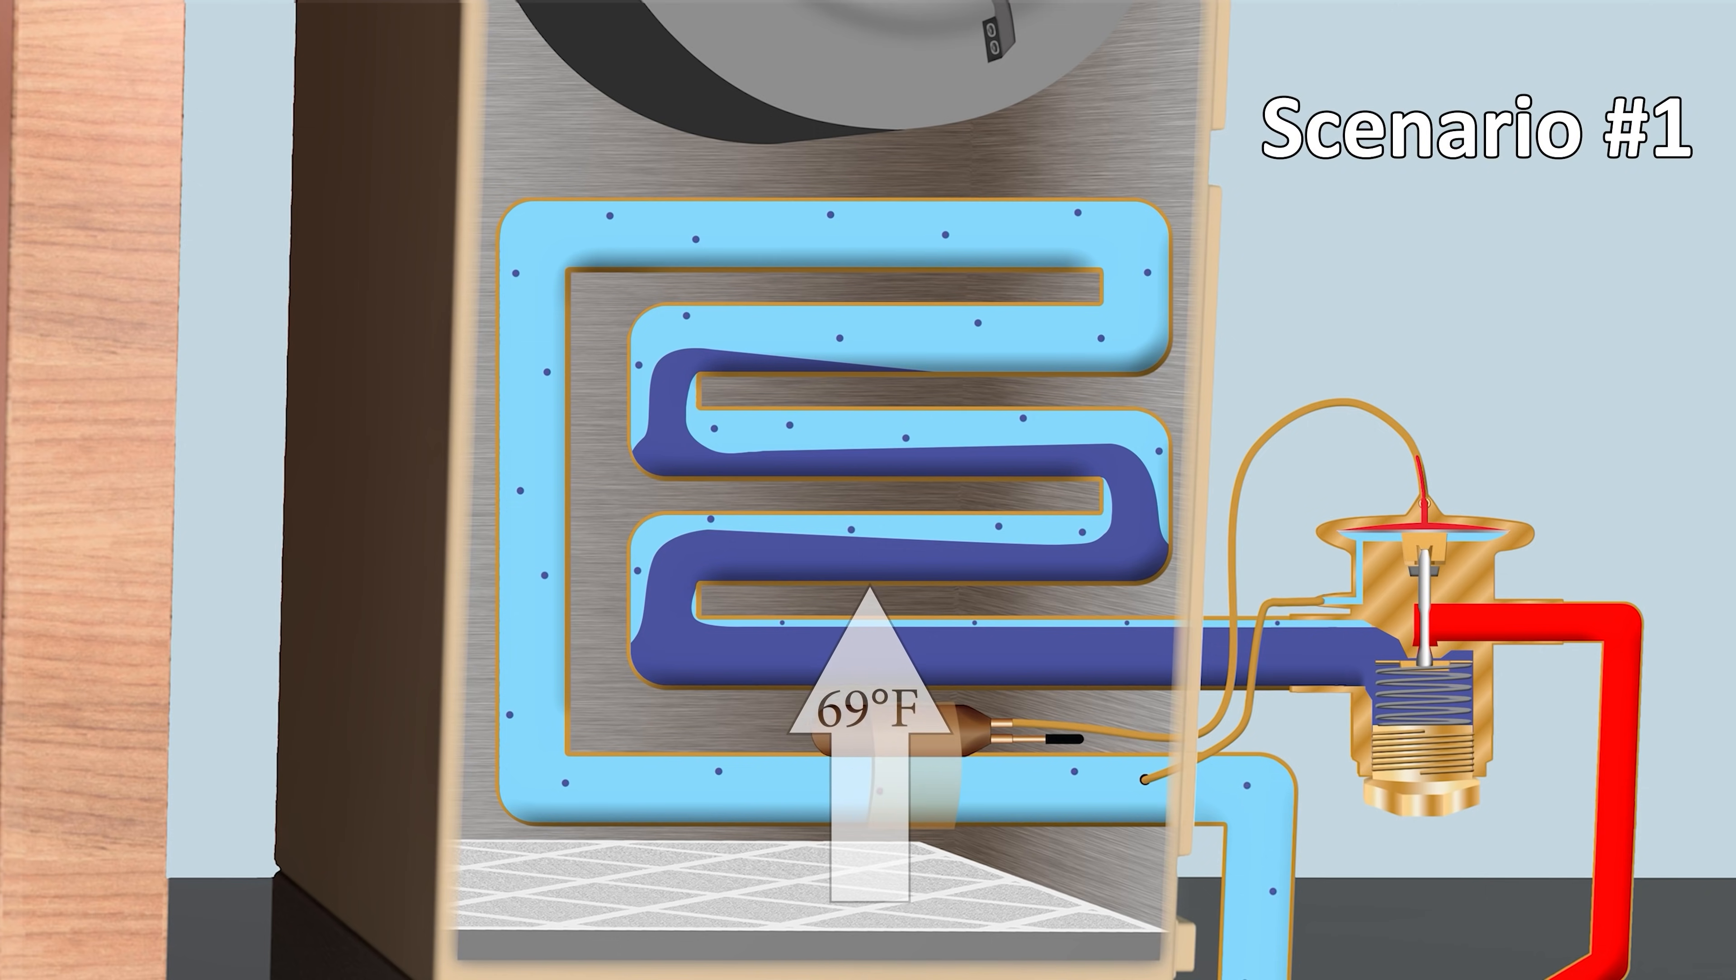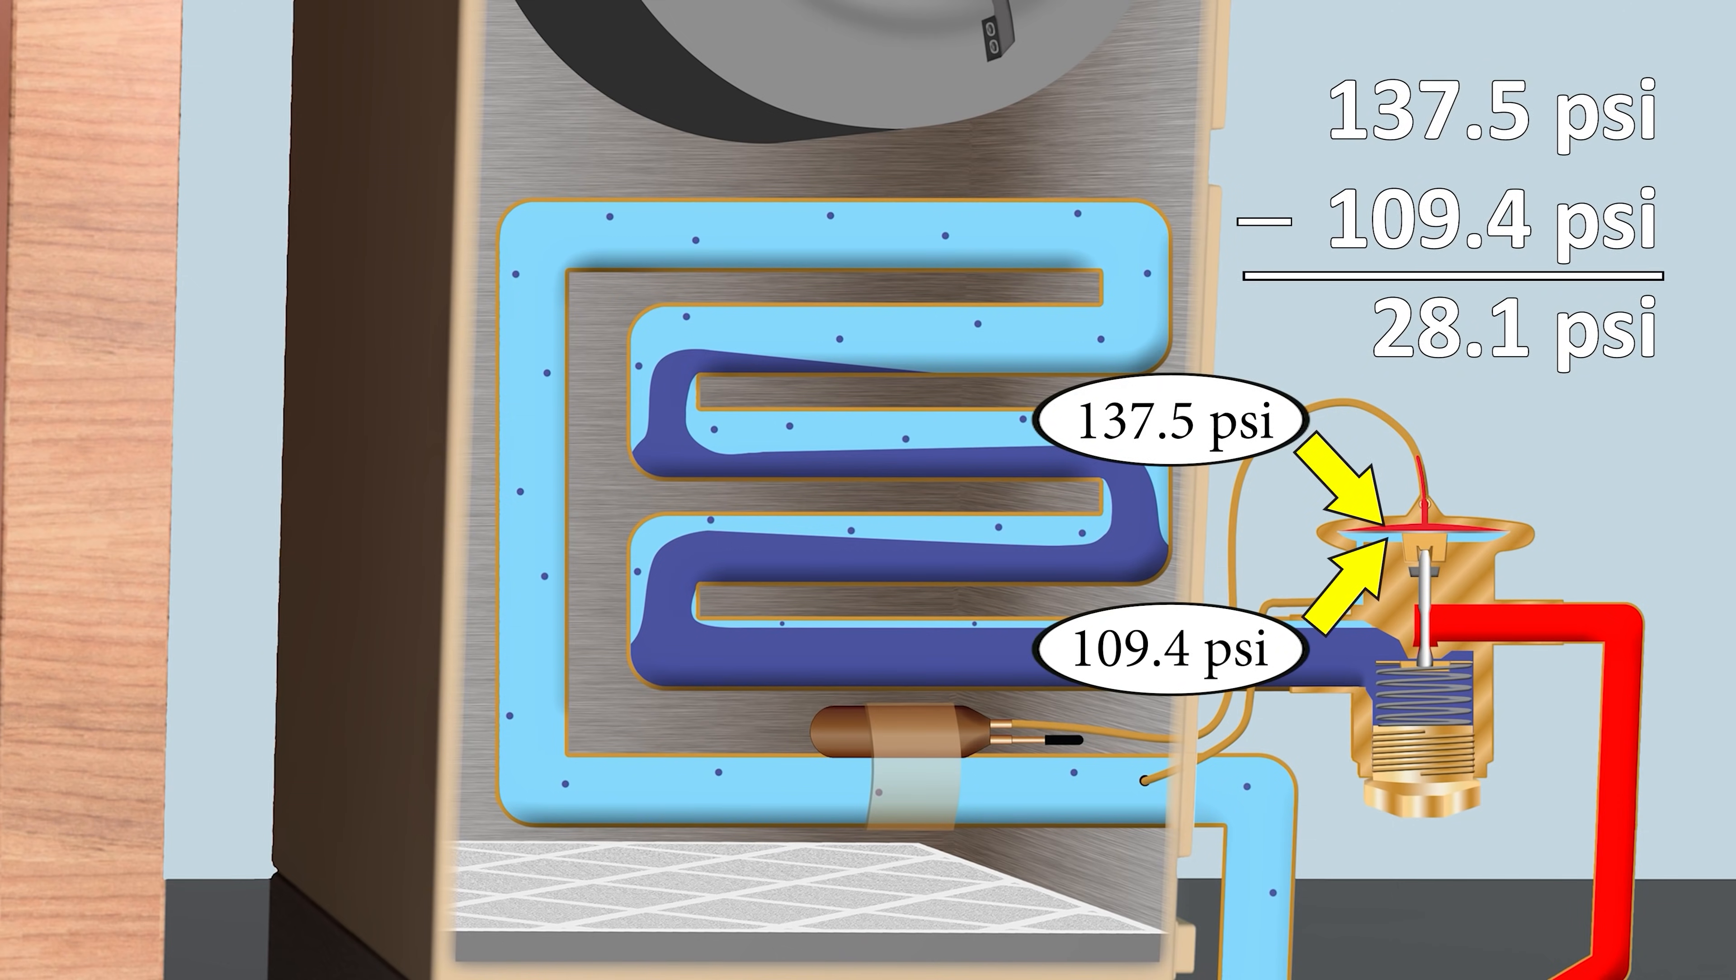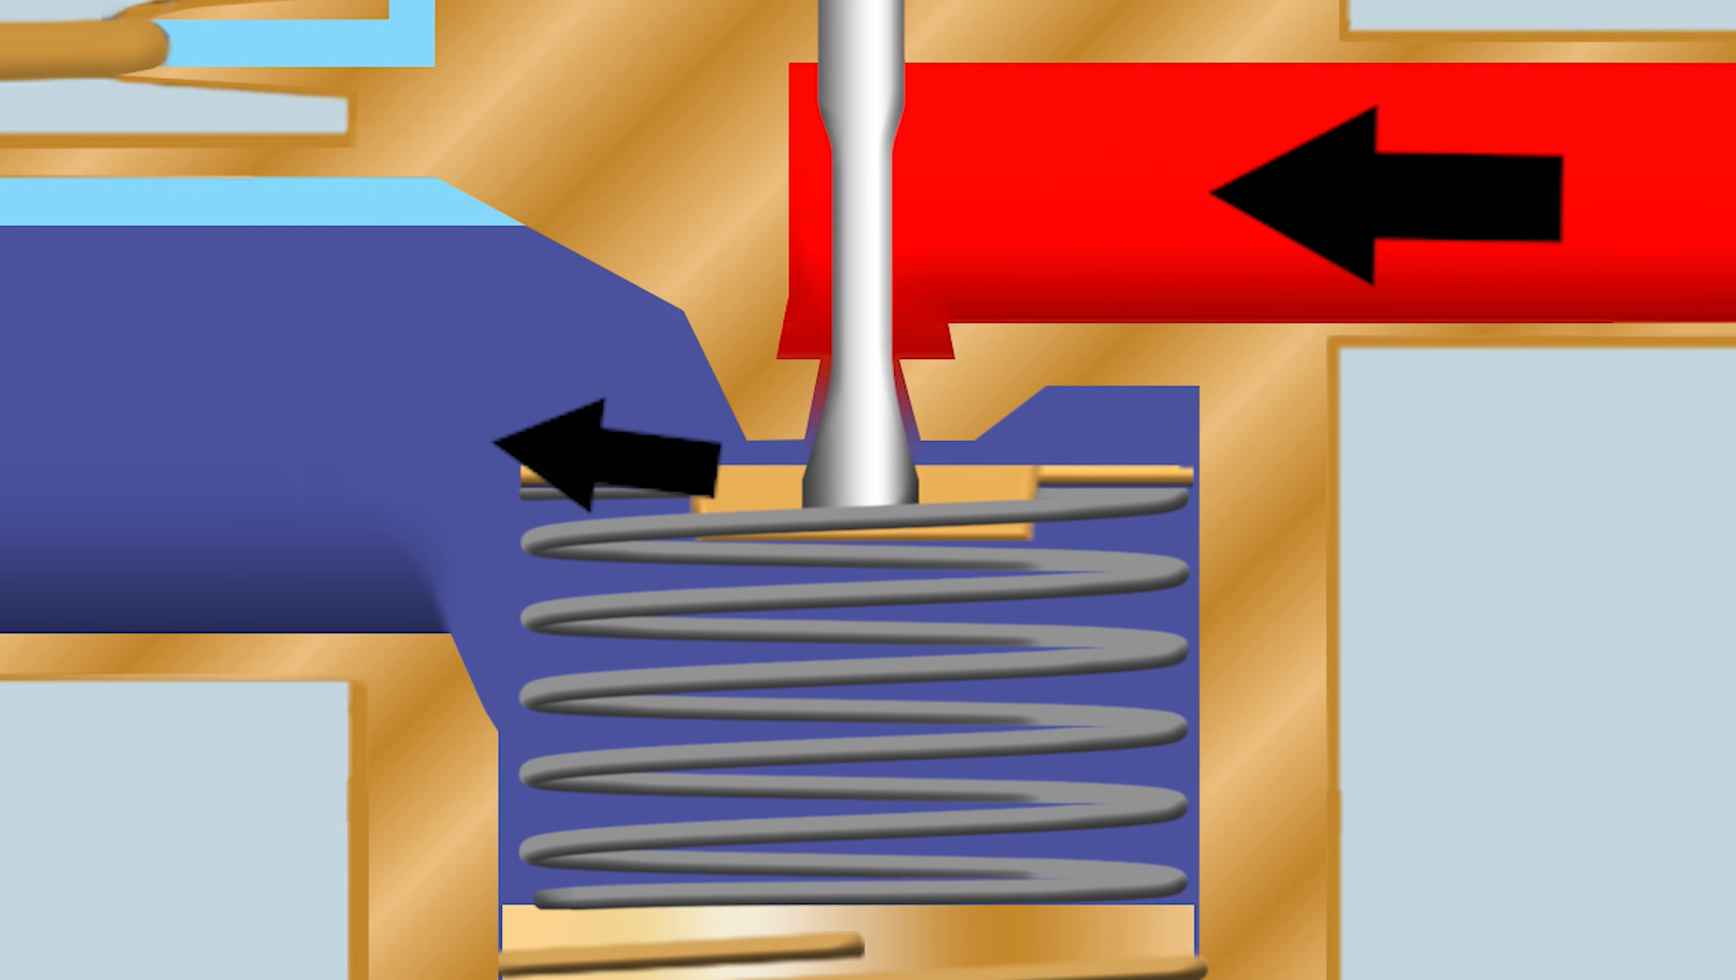Scenario one is where you have 71 degrees dry bulb temperature—it's low humidity, so that's the air temperature crossing that coil. In this case, we have a bulb temperature on the vapor line of 48 degrees. If we were to take a PT chart, we take 48 degrees and convert it to a saturated pressure of 137.5 psi. Then we also take an external equalization pressure of 109.4. So we take 137.5 minus 109.4, and we equal 28.1 psi as the spring pressure. Remember we're looking at P1 equals P2 plus P3. We're able to solve that equation to determine what the spring pressure is. You see this little tiny opening where the refrigerant is coming through the TXV. In the next two scenarios, there's going to be a higher heat load, so the opening in the middle of the TXV is going to be larger.